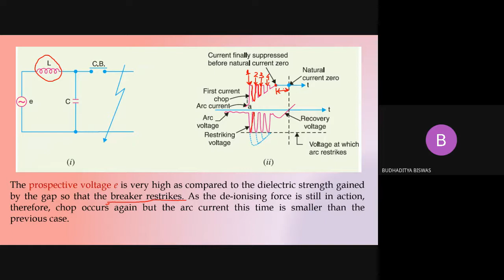This is an undesirable phenomenon, because due to this unnecessary oscillation will be there, and due to this oscillation some harmful inductive voltage may appear, or some transients may flow in the power system. It makes the quality of the power system bad. Now to prevent this, one method is there which is called resistance switching. This resistance switching is implemented inside the circuit breaker to prevent the current chopping.